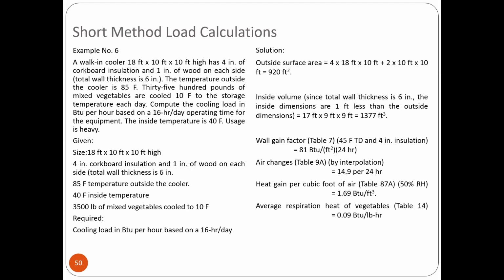Usage is heavy. Given: 18 feet by 10 feet by 10 feet high, 4-inch corkboard insulation and 1 inch of wood on each side, total wall thickness is 6 inches. 85 Fahrenheit temperature outside the cooler, 40 Fahrenheit inside temperature. 3,500 pounds of mixed vegetables cooled 10 Fahrenheit. Required is the cooling load in BTU per hour based on 16 hours per day operation.